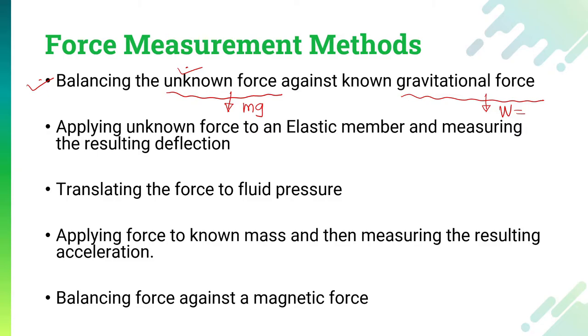The second method is by applying the unknown force to elastic members. Elastic members can be a spring, a beam, a cantilever, or a ring known as a proving ring. There are varieties of elastic members available. Whenever we apply force on those elastic members, they tend to deflect. The resultant deflection on that elastic member can be calibrated with the help of a force scale, and we can measure the force in terms of deflection.